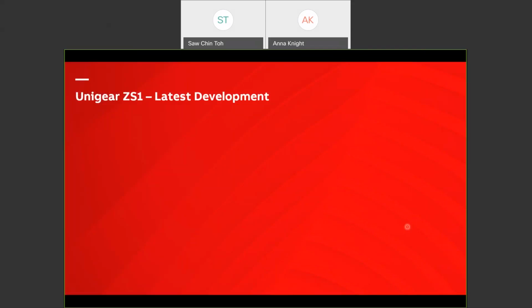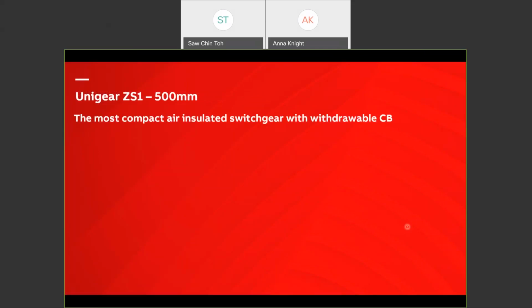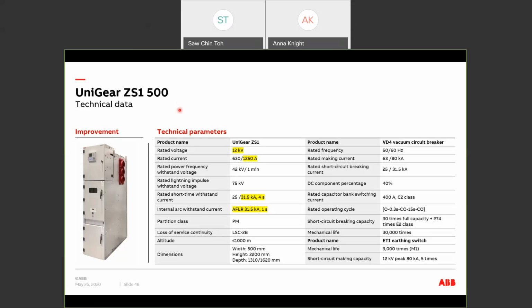Now I would like to share with you our latest product launches. We have now improved the footprint of UniGear ZS1 by introducing the UniGear ZS1 500mm wide panel. This is the most compact air insulated switchgear with withdrawable circuit breakers. Although the cabinet width is reduced from 650 millimeters to 500 millimeters, the technical parameters have not been lowered. The panel is rated at 12 kV, 1250 amps, 31.5 kA 4 second withstand, and internal arc fault of AFLR 31.5 kA 1 second.